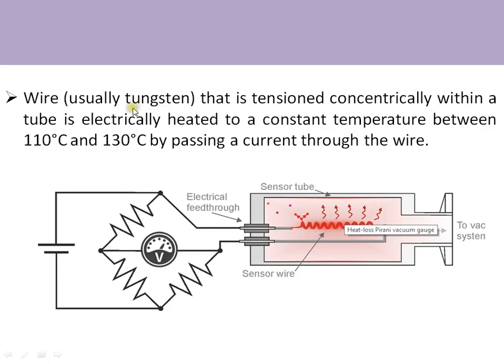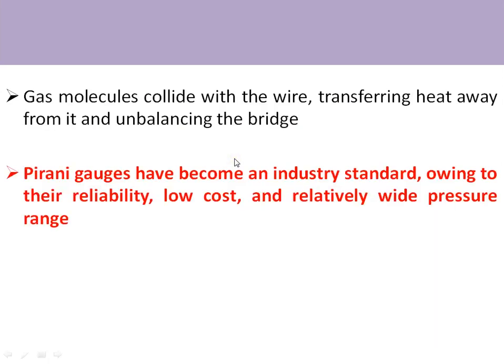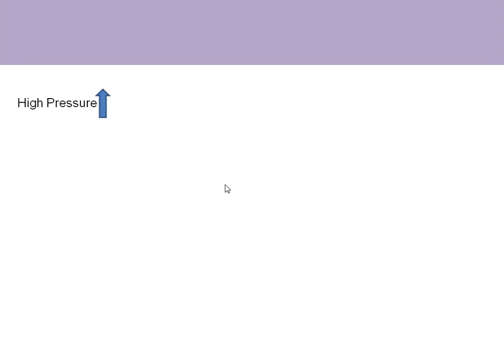The wire is tensioned within a tube and electrically heated to a constant temperature between 110 and 130 degrees Celsius by passing a current through it. Gas molecules collide with the wire, transferring heat from it and unbalancing the bridge. This unbalance produces an output voltage measured using the Wheatstone bridge. The Pirani gauge has become a wide industry standard because of its high reliability, low cost, and relatively wide pressure range — from atmospheric pressure down to 10⁻⁵ millibar.